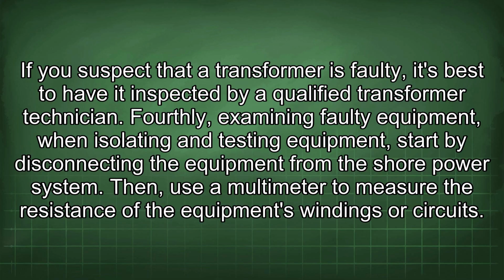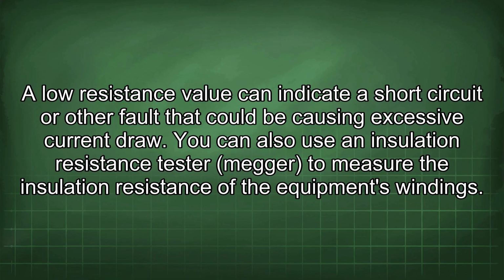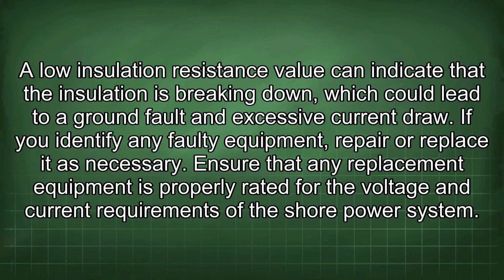Then, use a multimeter to measure the resistance of the equipment's windings or circuits. A low resistance value can indicate a short circuit or other fault that could be causing excessive current draw. You can also use an insulation resistance tester to measure the insulation resistance of the equipment's windings. A low insulation resistance value can indicate that the insulation is breaking down, which could lead to ground fault and excessive current draw. If you identify any faulty equipment, repair or replace it as necessary.